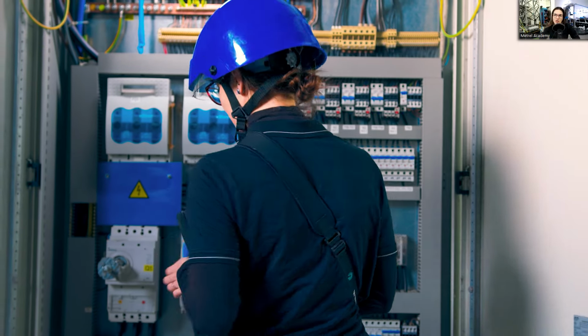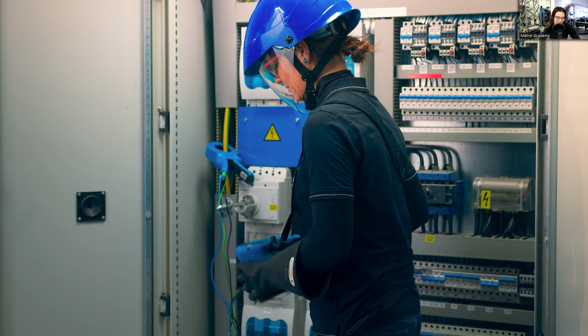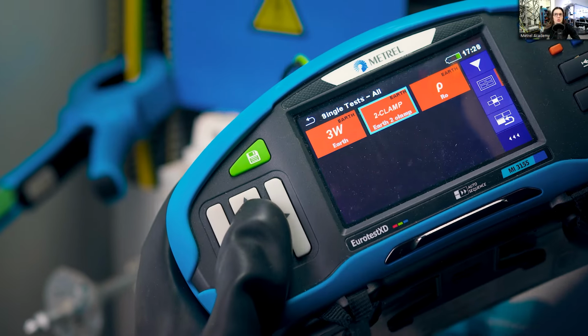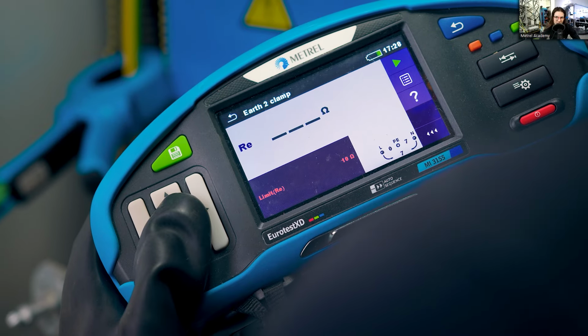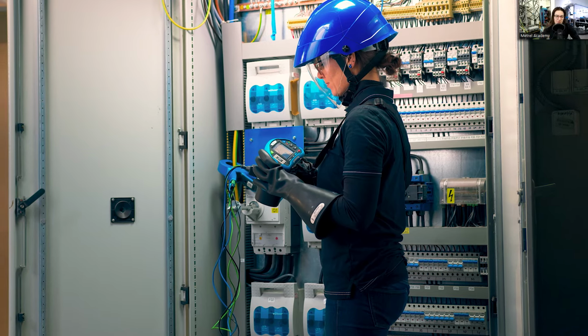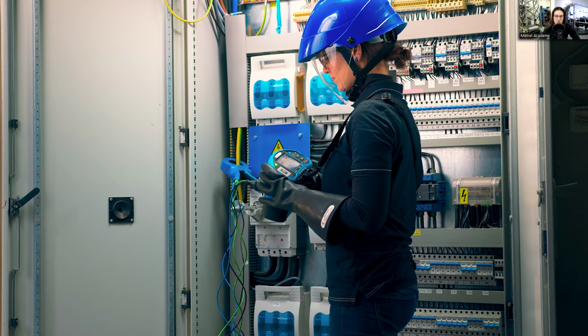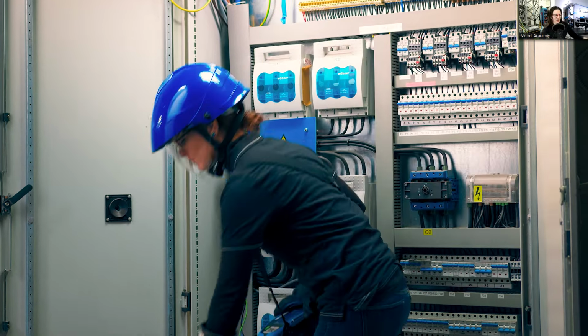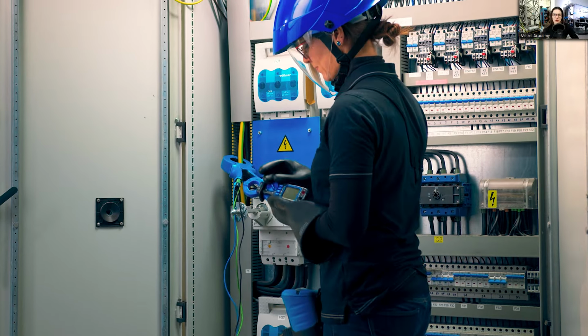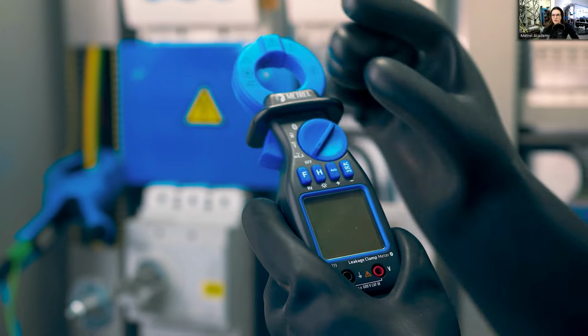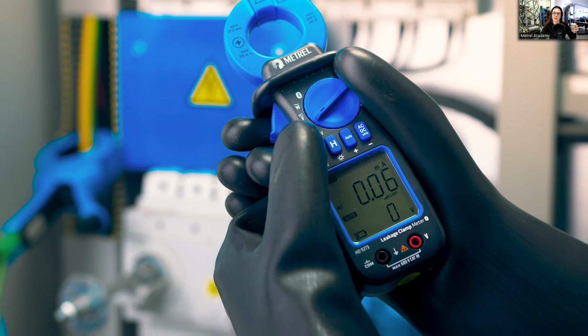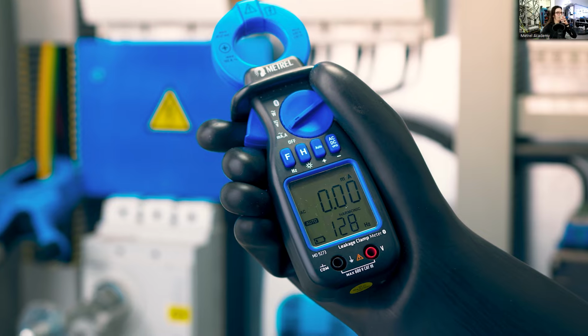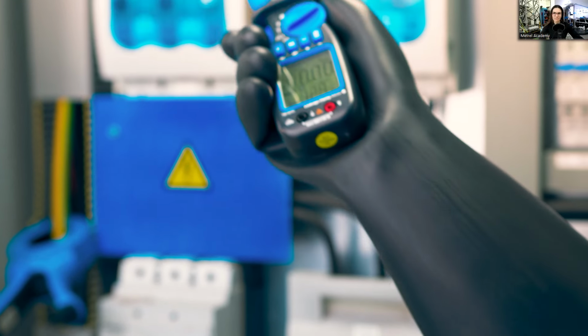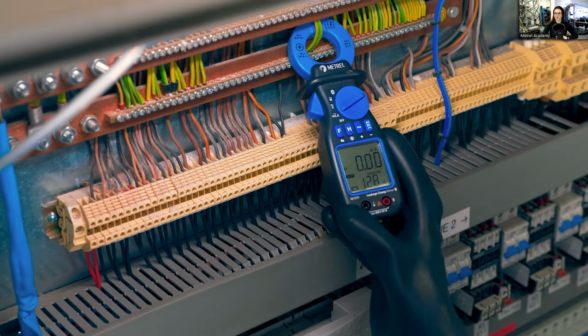So again, we have an industrial distribution board. We use the generator clamp A1019 to generate the signal into the main protective earth wire. So we just set up the protective earth two-clamp method on the instrument, and then we use the clamp with the 128 Hertz filter activated. And now we look where this signal is flowing.